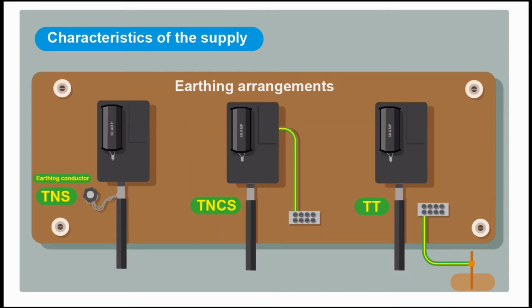Right, we have to record the earthing arrangements. In the UK, there's three main types. The first one is TNS. This is where we use the supply cable as the earth return path. We have the earthing conductor connected to the metal sheath of the cable, and that goes onto the MET.